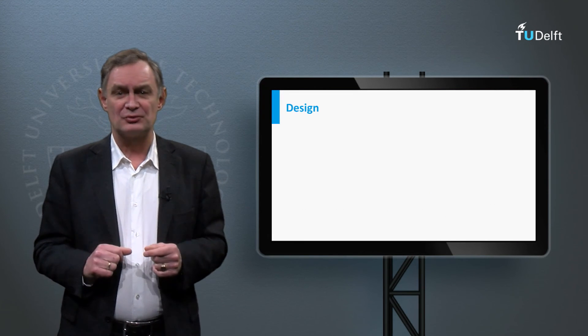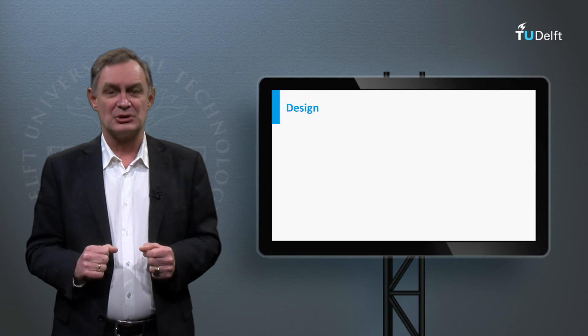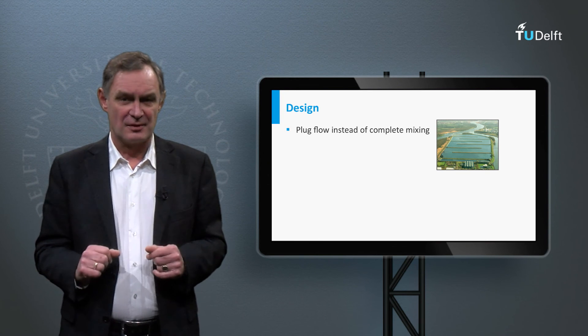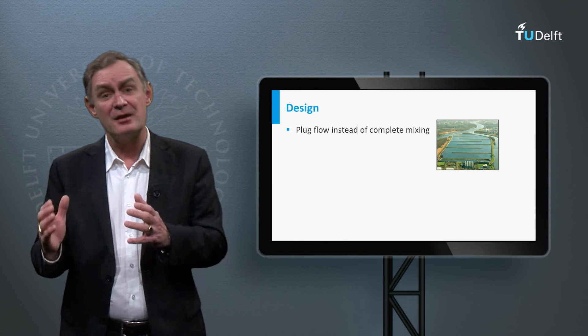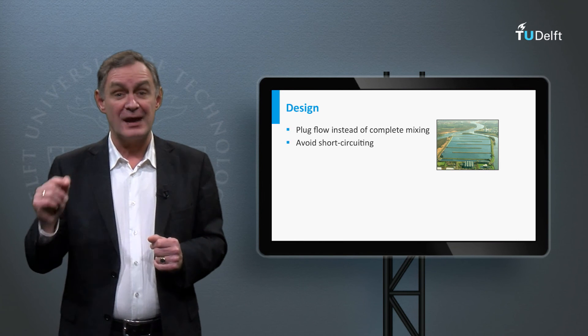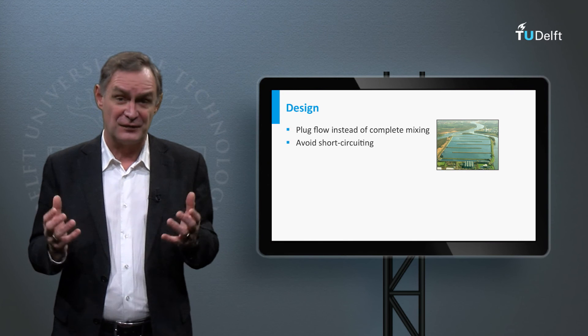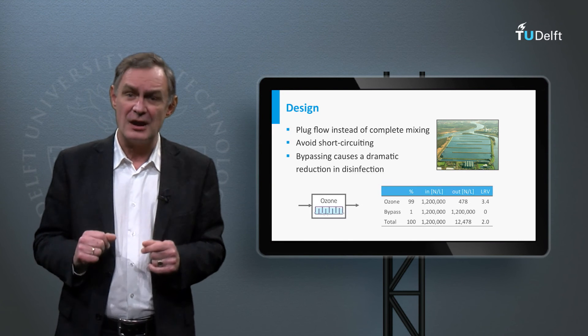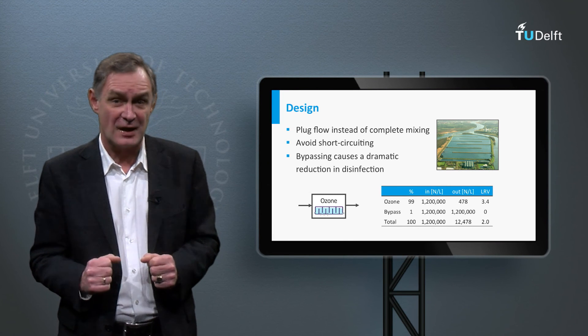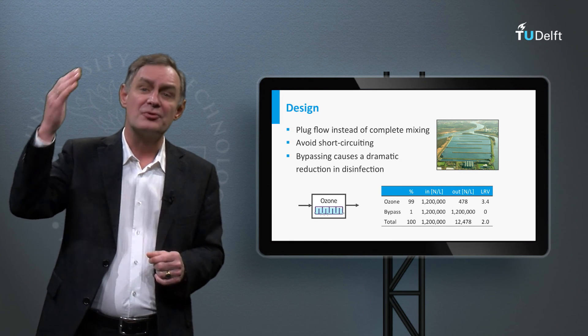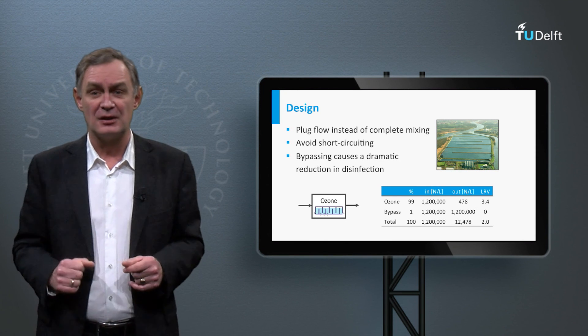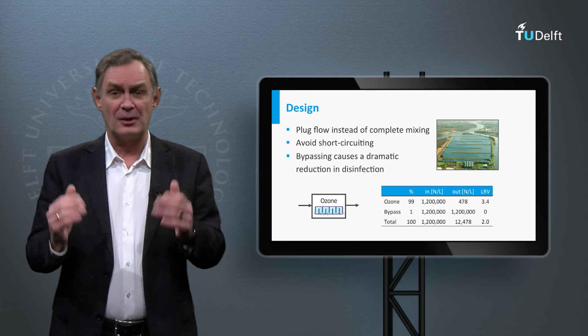Plug flow tanks are more efficient in the removal of pathogenic microorganisms than completely mixed reactors. Short circuiting should also be avoided, since it has a negative effect on the efficiency of disinfection. Here you can see an example of the dramatic effect of only 1% bypass on the total log reduction value of the system – it decreases from 3.4 to 2. This shows that not only a sufficient disinfectant dose is important, but also a proper design is required.